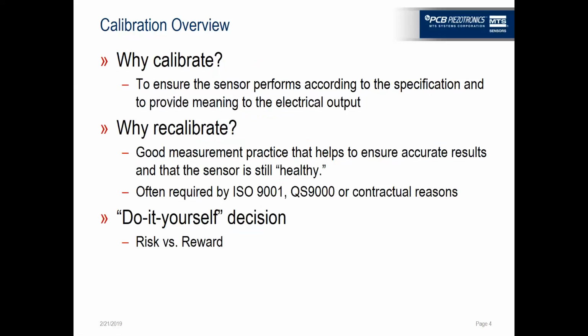So why do we calibrate things? Well, the obvious reason is to make sure that the performance of the sensor is according to its specification, and to make sure that we collect meaningful data. Comparing volts to volts to volts when it has no meaning behind it, meaning I've got a microphone that's outputting 1 volt, but I don't know what the sound pressure equivalent to that is on the other terminal. Another reason to calibrate is to make sure that your sensor remains healthy. So why recalibrate? Making sure that the sensor doesn't shift over time.